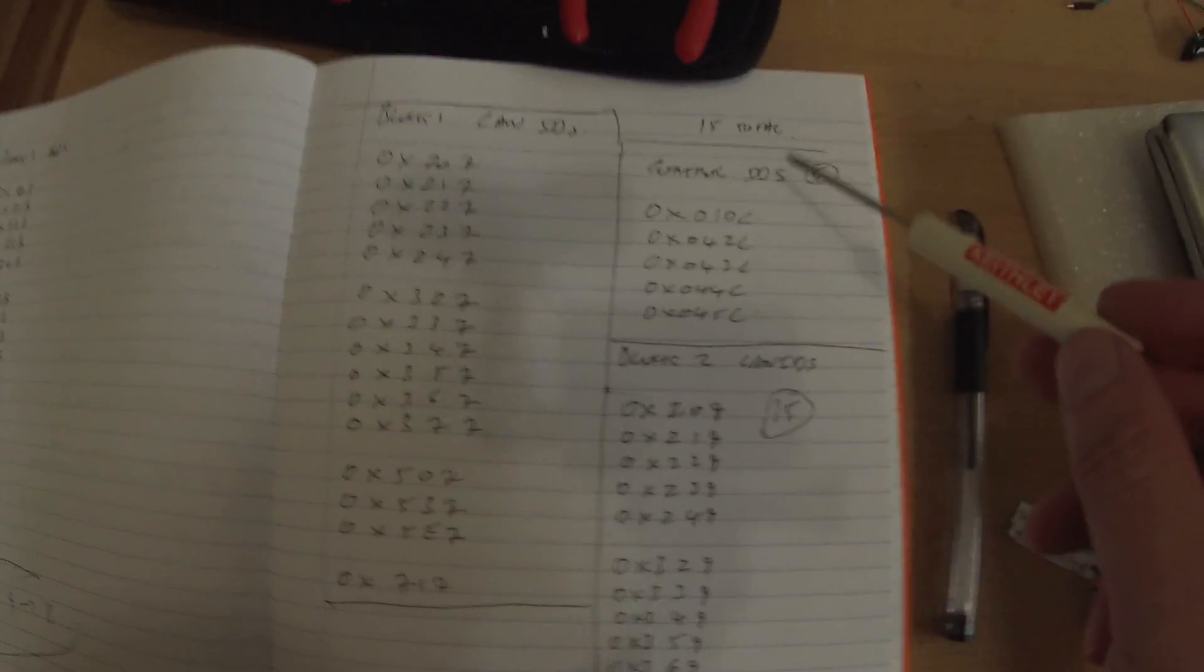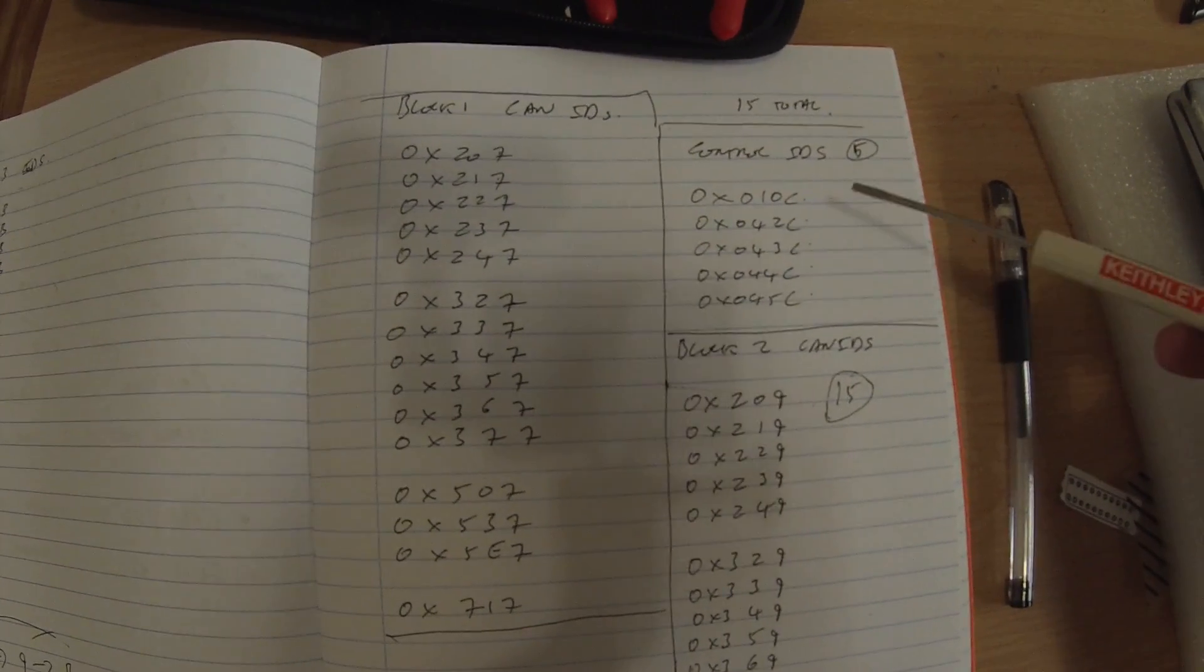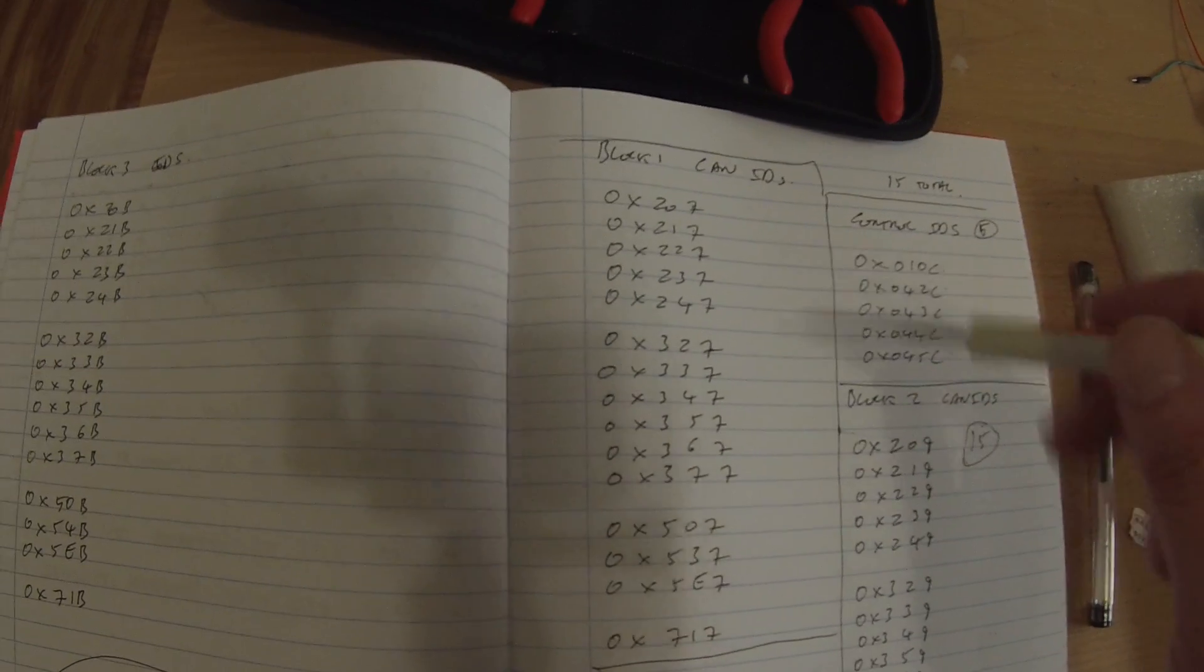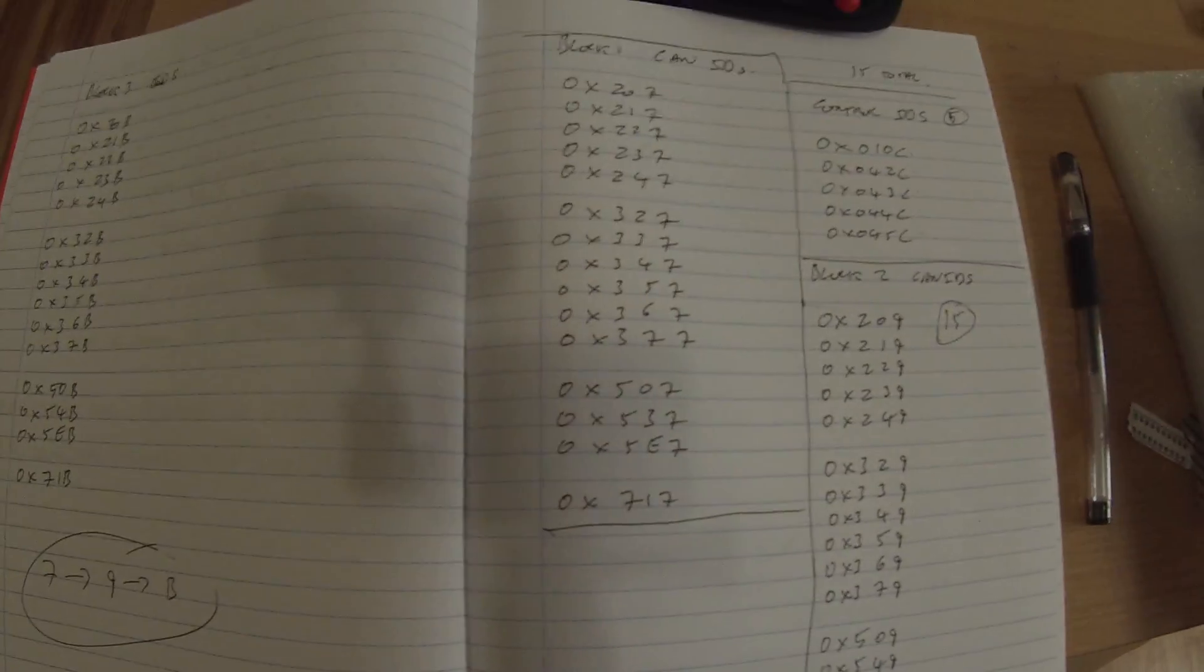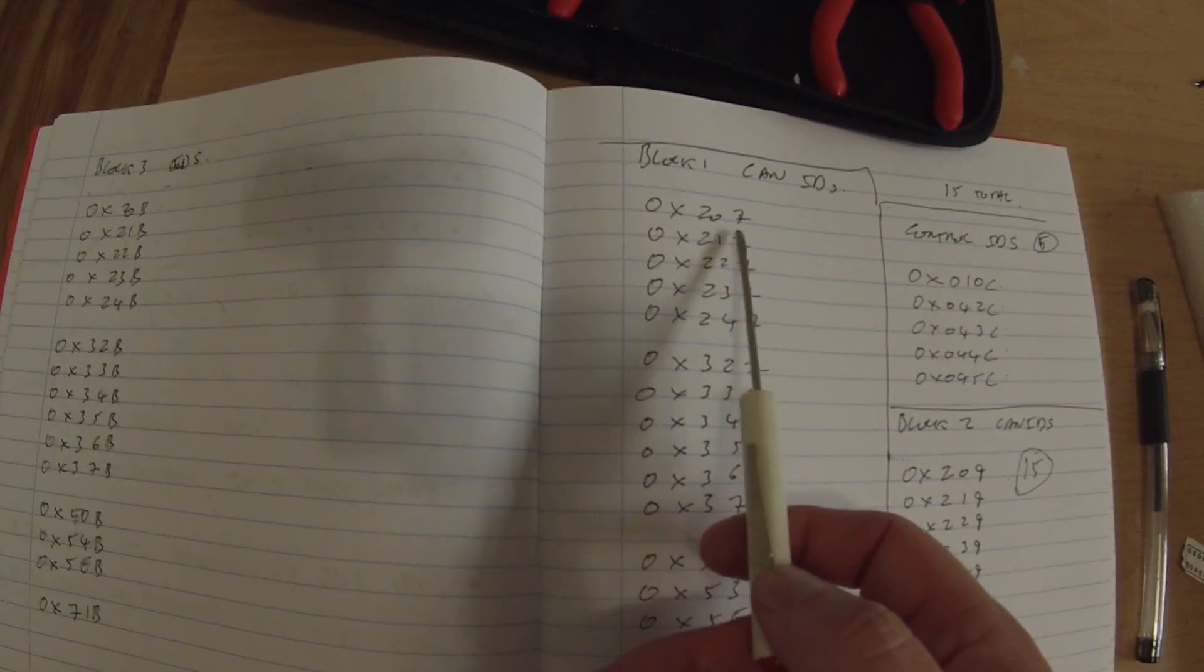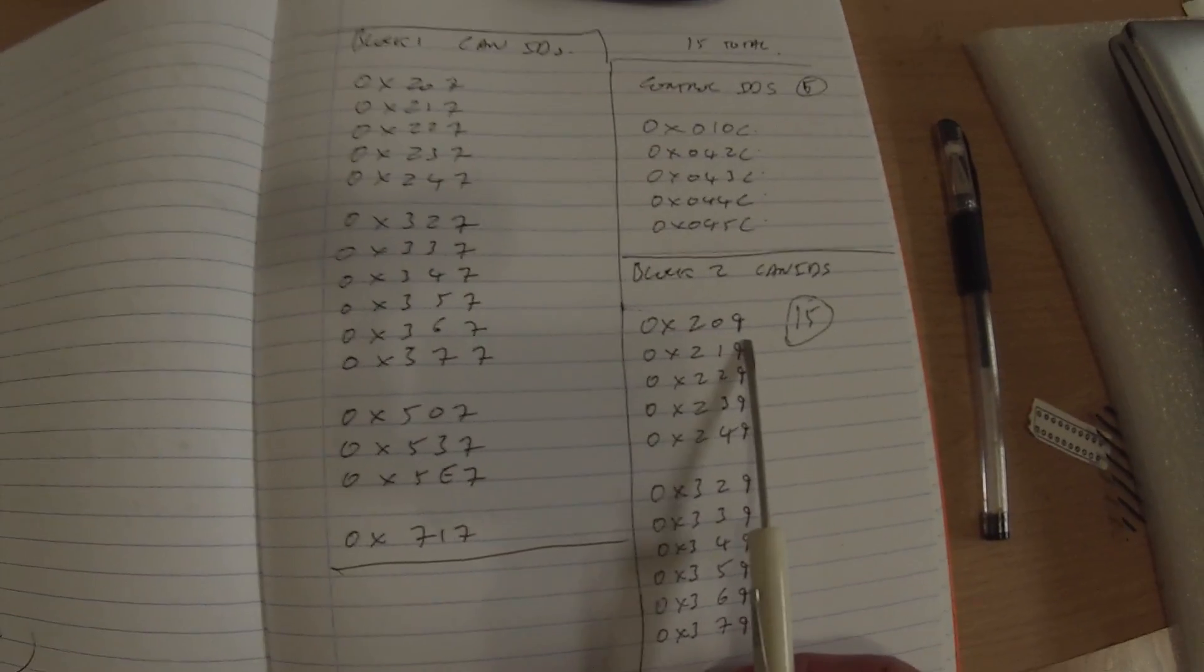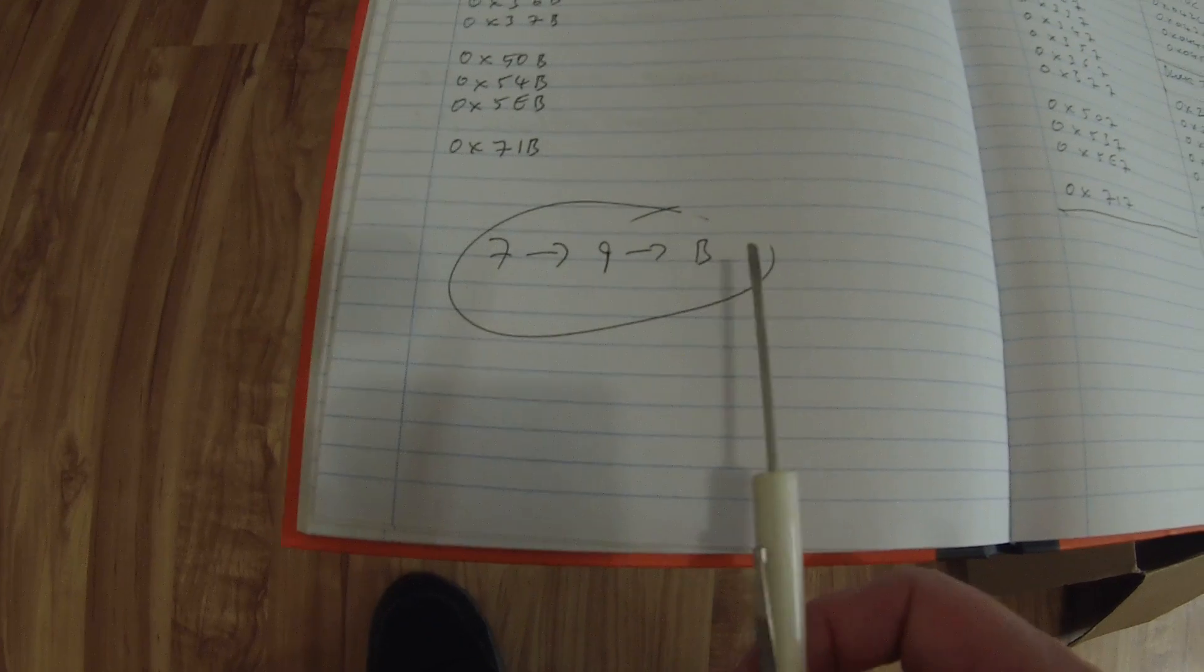So the logic board itself puts out five CAN IDs, pretty much the numbers that you see here. Now where it gets interesting are the CAN IDs that the power modules put out. They put out 15, they're in these kind of blocks. I've kind of broken them into the 2s, 3s, 5, and 7 ID. And you'll see here, if we take the first ID from block one, it's 0x207. The first ID from block 2 is 0x209, and from block 3 is 0x20B.